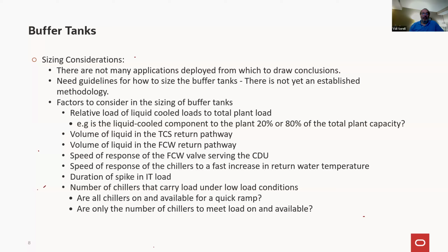Yeah, and it's clearly not a trivial pursuit to come up with these point items that need to be addressed when sizing that buffer tank. And it's a complicated series of design decisions that need to be made to get to that decision. Do I need a buffer tank? And if I do, how big is it? Where is the best place to put it? And I wanted to highlight the difference between sizing the thermal storage and sizing a buffer tank. With thermal storage, it's easy. You have, let's say, 1,000 gallons per minute, and you know that you can lose the chillers for 5 minutes.